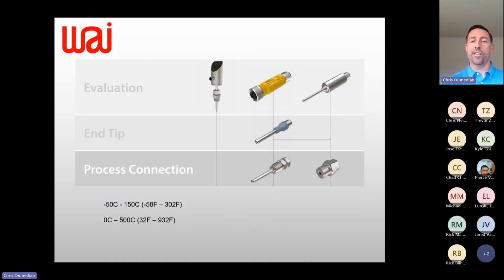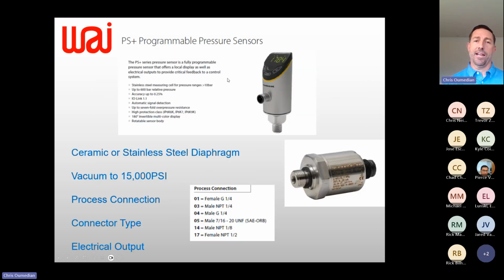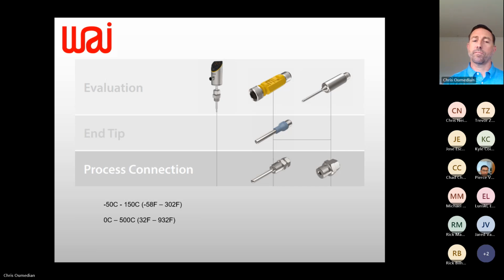Any questions on RTDs or TTM? I left out, I'm realizing, the data sheet or the pictorial of our temperature sensor, but it's identical to this one here, which is our pressure sensor. So same thing with your RTD probe, and it's putting out a 4 to 20 milliamp signal, programmable LCD color change, similar functionality, different measuring principle. Questions on RTDs?